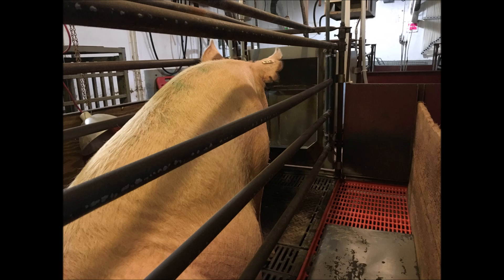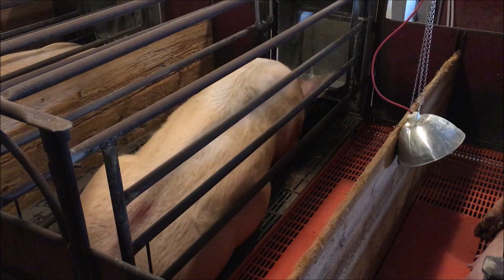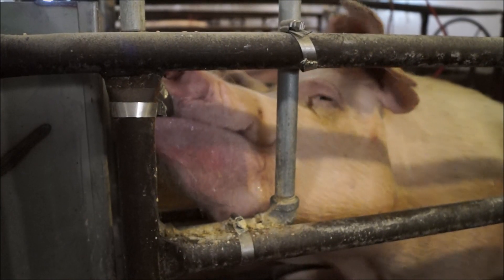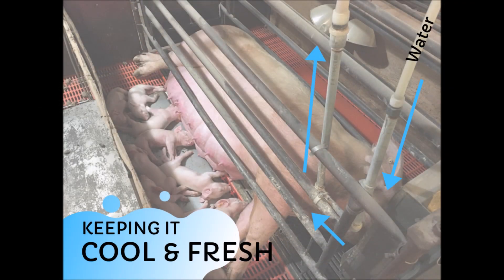From the main holding areas, chilled water travels to the sow cooling pads that are located under the shoulder of the sow in the stall. This section is made of cast iron and neatly fits into the existing floor. The cool water snakes through the piping located under the pad. When the chilled water reaches the sows, the water is 65 to 70 degrees Fahrenheit. At this point, the water rises about 4 to 5 degrees due to the heat transfer from the sow through the floor surface to the water. The warmed water then travels back to the heat pump where it is cooled through transfer of heat to the warm water loop that heats piglets. The chilled water for the drinkers goes through a very similar process as the cooling pad water. The drinking water is pulled from the research station's well, same as the other barns located on the farm. Any extra heat that is present in the well water is transferred by the heat pump to the warm water loop for heating piglets.